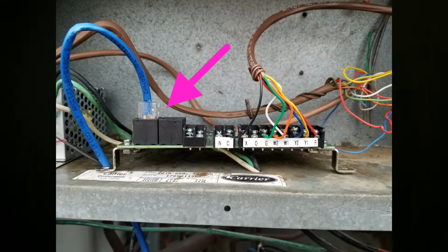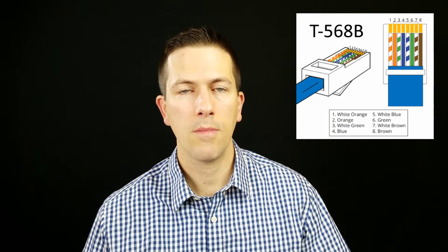When the thermostat signals are detected, they are communicated to the OptumSoft data collection unit for analysis and anomaly detection. The RJ45 port on the OptumSoft thermostat board is used for sending those signals to the data collection unit. Cat5e or Cat6 should be used to connect the OptumSoft thermostat sensor to the DCU. If your application is for HVAC and on the exterior of a building, then you should use cable rated for outdoors. This cable should be used with the T568B wiring pattern.